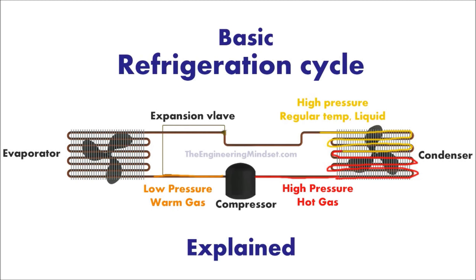Stage 3 happens at the expansion valve. The refrigerant enters from the condenser as a high pressure, regular temperature liquid. The valve regulates the flow of refrigerant around the system and into the evaporator. It does this using a diaphragm. Inside the valve body here is a diaphragm. And the diaphragm is connected to a thermal bulb over here on the exit of the evaporator. And it's connected via capillary tube, that thin tube.